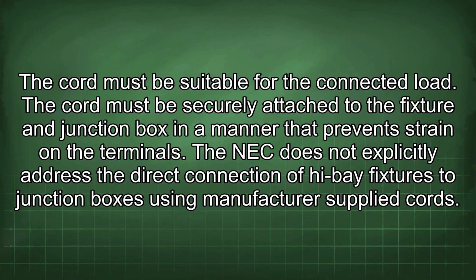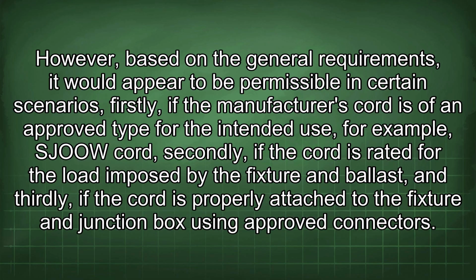terminals. The NEC does not explicitly address the direct connection of high-bay fixtures to junction boxes using manufacturer-supplied cords. However, based on the general requirements, it would appear to be permissible in certain scenarios. Firstly, if the manufacturer's cord is of an approved type for the intended use, for example, SJ cord. Secondly, if the cord is rated for the load imposed by the fixture and ballast. And thirdly, if the cord is properly attached to the fixture and junction box using approved connectors.